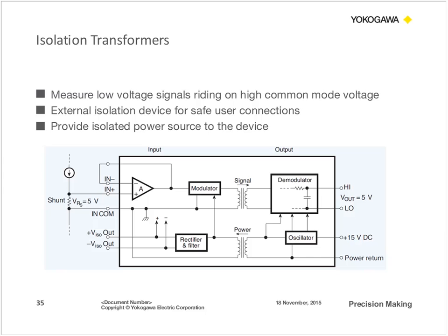External isolation devices can be used to safely separate the device from the power mains, as well as separate the device from the measuring instrument. And it can also provide you the benefit of providing a power source to the motor device, or whatever it may be that you're connecting to.